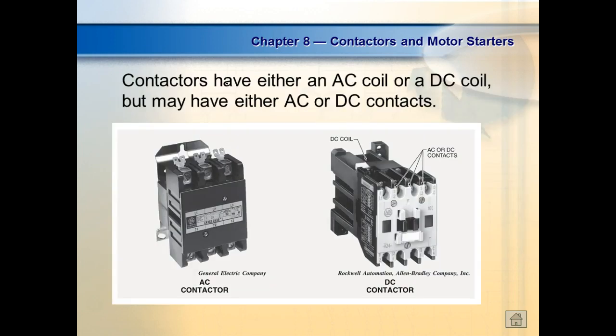So what we need to understand is what the coil controls, what the contacts control, and what the solenoid requires would be two different things. So I could have an AC contactor, which means it's got an AC coil controlling the DC circuit, right? Or I can have a DC coil controlling the contactor controlling the AC circuit. That's very common. Are we okay?